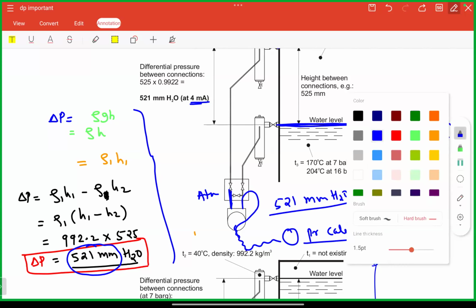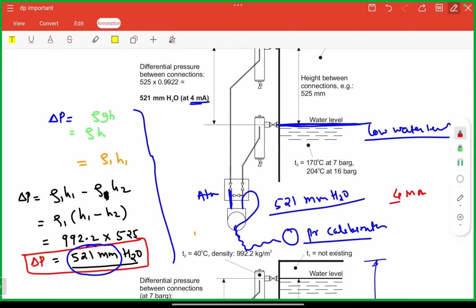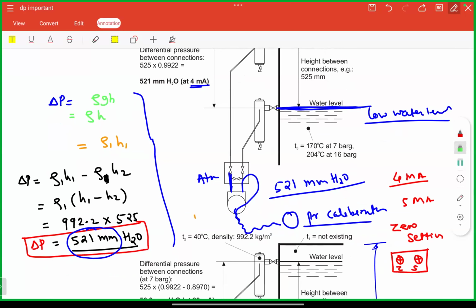So what will happen? Output signal should be 4 milliamp. But if it is not 4 milliamp, let's say it is showing you 5 milliamp, so what do you require to do? You require to adjust the zero setting. So if you look into the DP transmitter controller, there will be two knobs. Okay, zero setting and span setting. You have applied differential pressure corresponding to 521 mm of water column. Corresponding to that, you should receive the output signal of 4 milliamp. If it is not generating 4 milliamp, with the help of a screwdriver you are going to adjust your zero setting knob till you get a 4 milliamp output signal.